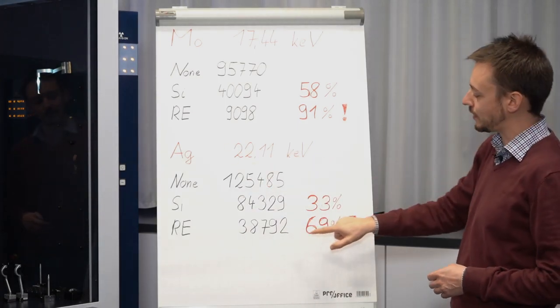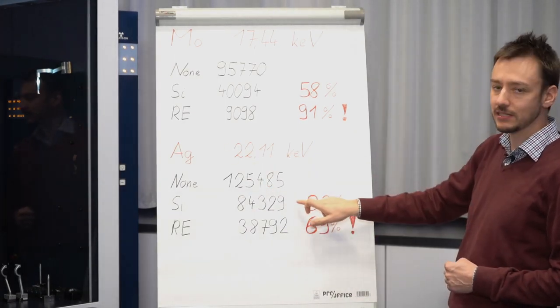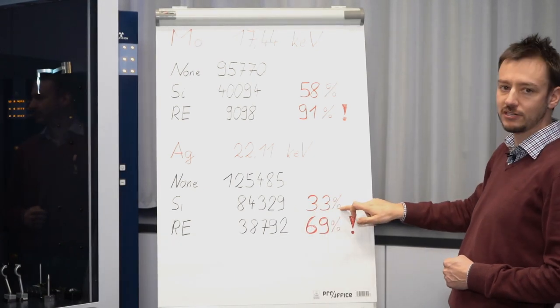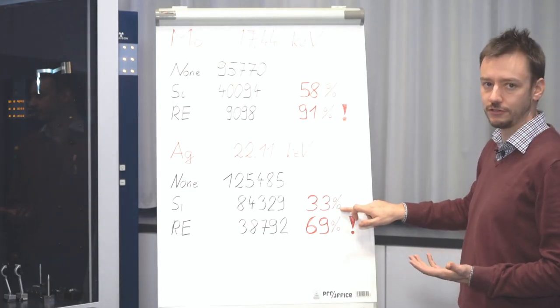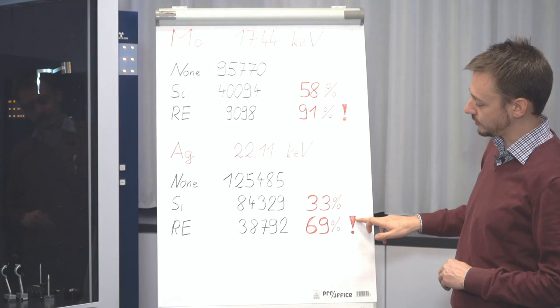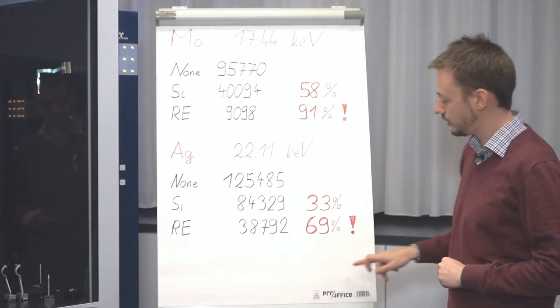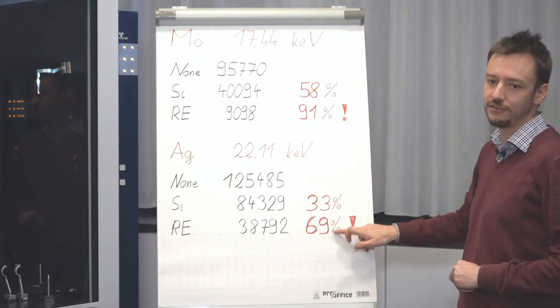Again same setup for the measurement but what you get with silver radiation is only 33 percent on the silicon chip which means two photons out of three are lost. You measure only one third of the photons from your crystal while with the rare earth x-ray converter with 70 percent you are still very very good.